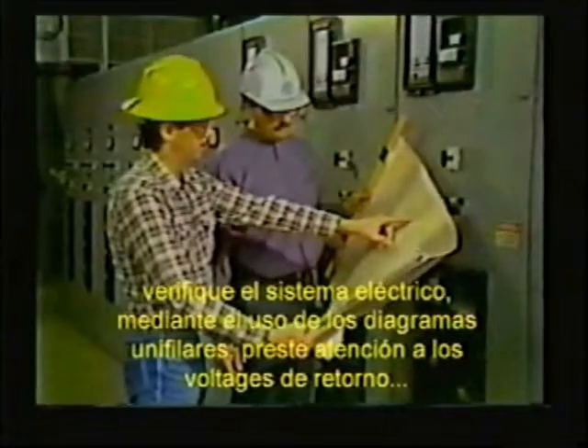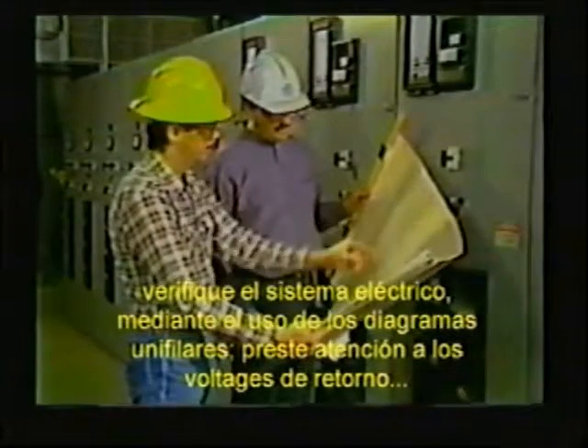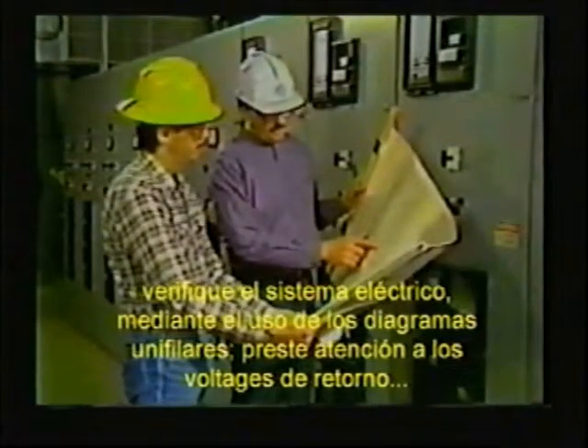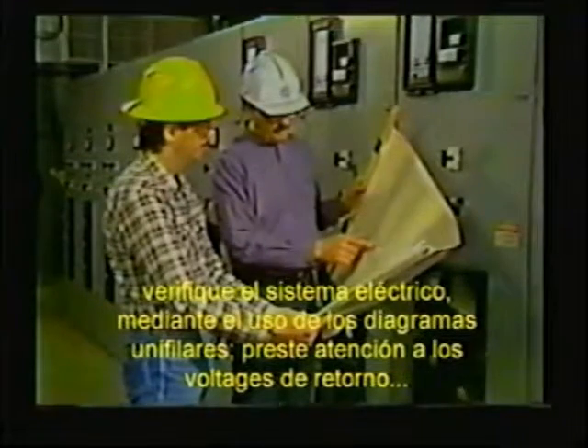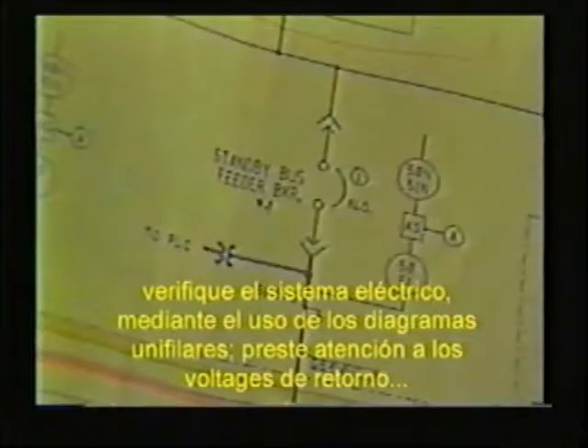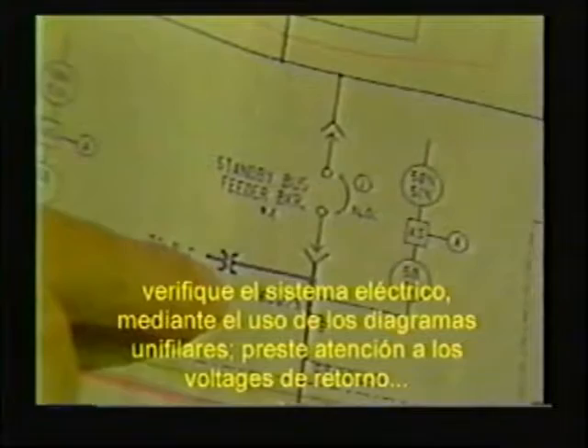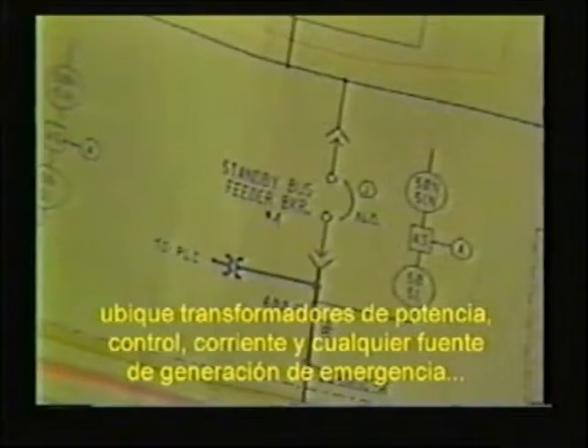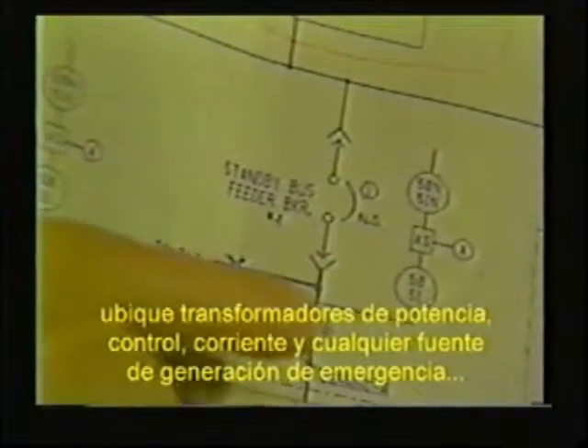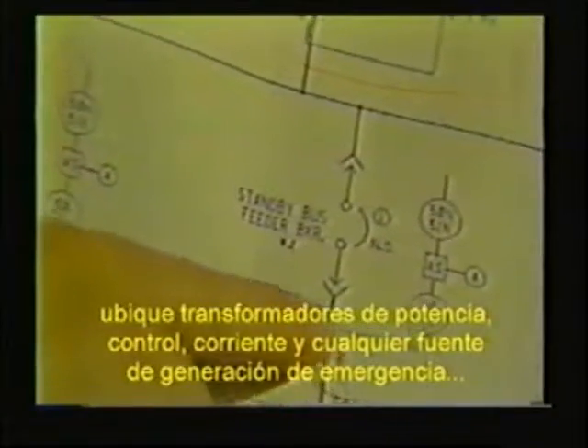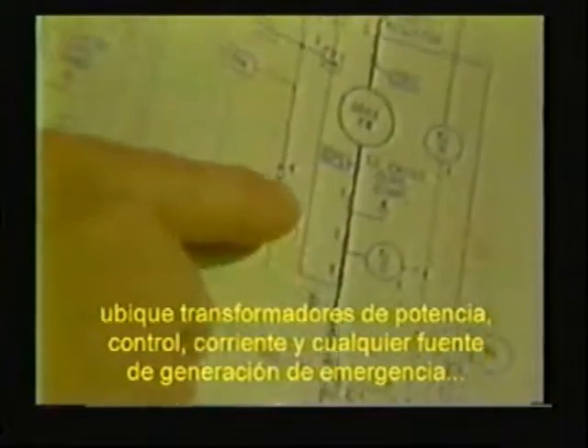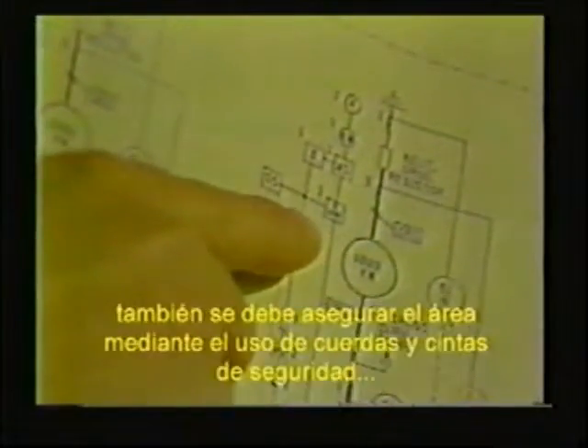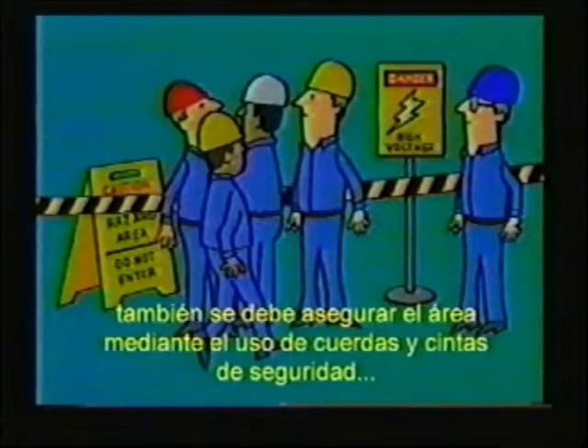He familiarizes himself with the power system by checking the system one-line diagram for all potential sources of current, including secondary sources such as backfeed voltages through potential transformers, control power transformers, current transformers, and emergency power sources such as emergency generators. Dave also secures the area using ropes, warning tape, and danger signs to keep traffic to a minimum.